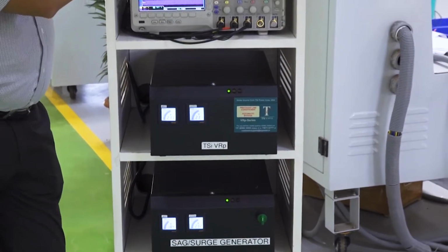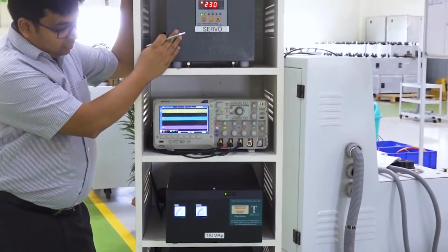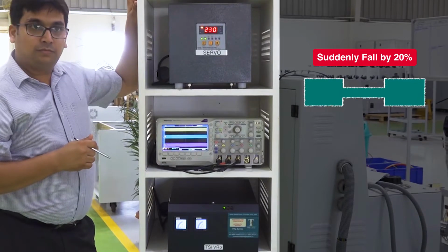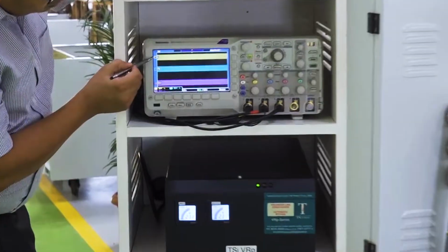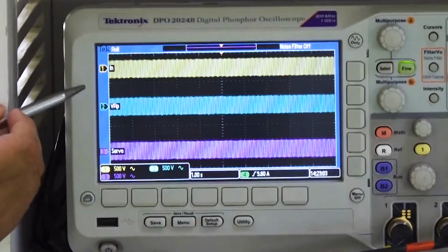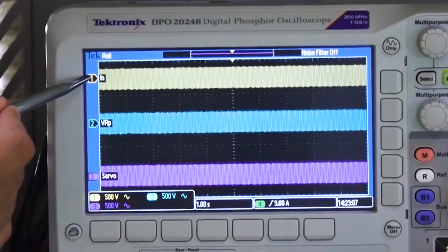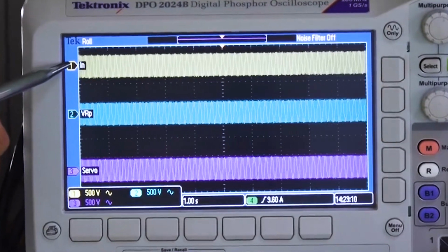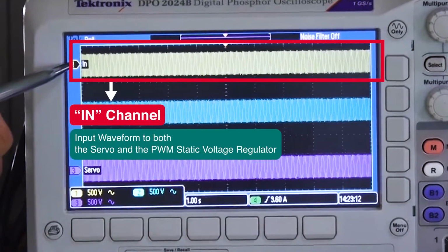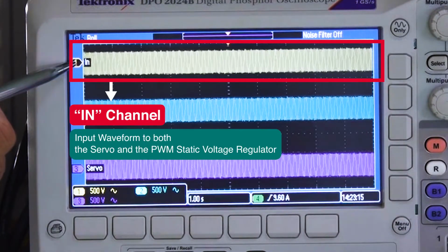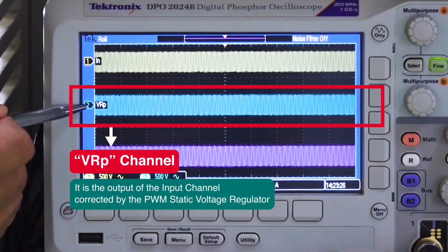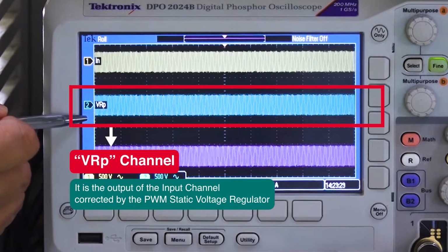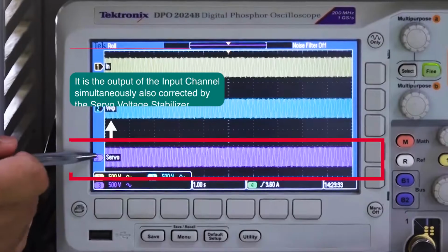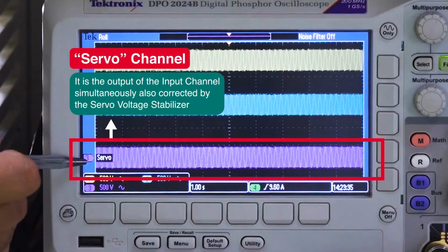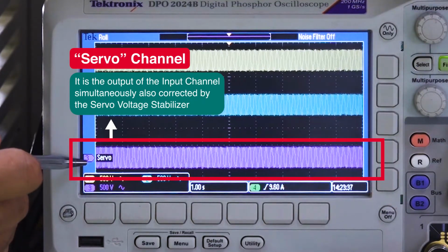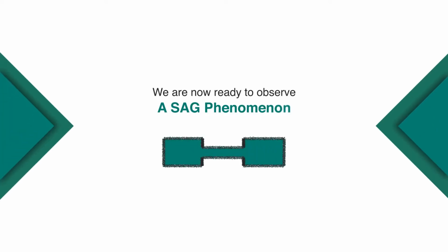Accordingly, the input voltage to both the static voltage regulator as well as the servo voltage stabilizer will either suddenly fall by 20% or suddenly rise by 20%. To monitor the resultant performance, there is an oscilloscope with 3 channels. As you can see here, this yellow top channel records the voltage waveform generated by the sag surge generator. This channel is marked as input waveform to both the servo and the static voltage regulator. This waveform is then corrected by the static voltage regulator, whose output is recorded in this channel marked as VRP. This waveform is simultaneously also corrected by the servo voltage stabilizer, whose output is recorded in this channel, marked as servo.